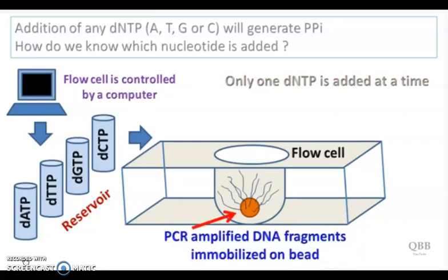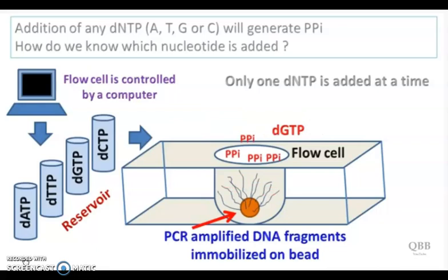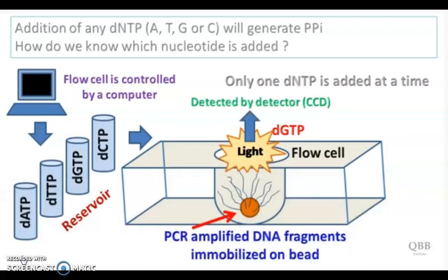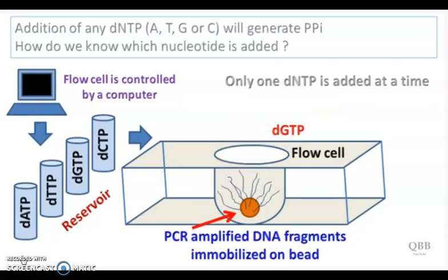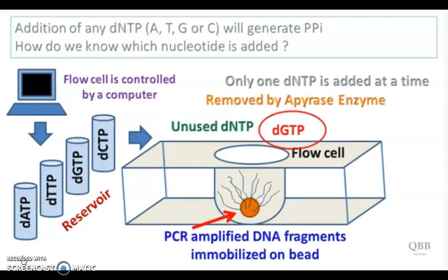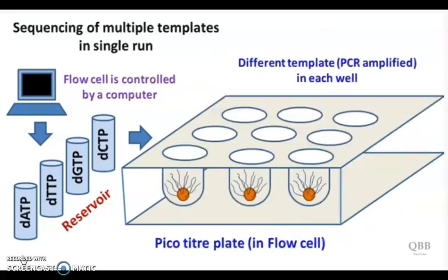Because of this, when a dNTP is added, a large number of pyrophosphate molecules are released. Hence, the light produced is intense and easily detected by the sensor. If dNTP is not incorporated, no light is detected. Hence, the sequence information of the DNA can be easily obtained with light. Unused dNTPs in the flow cell can be removed by the apyrase enzyme.